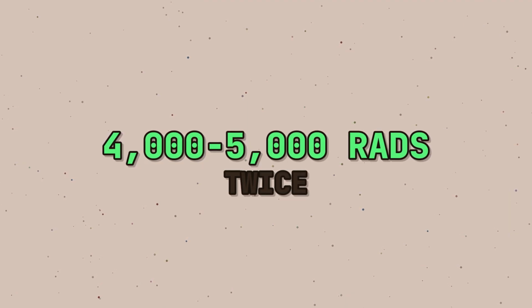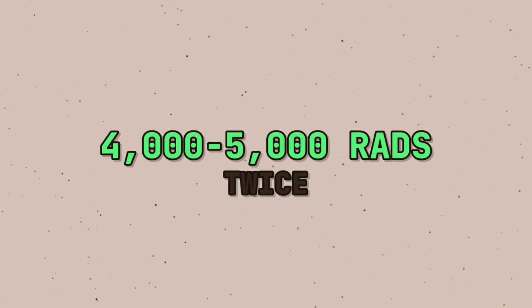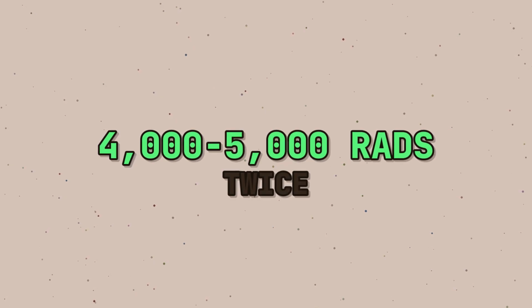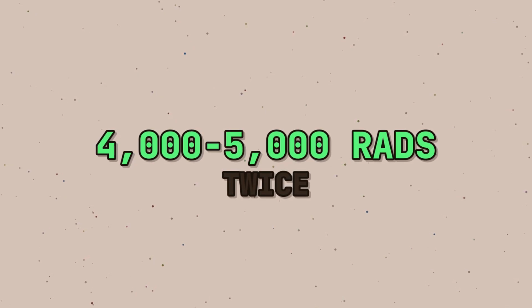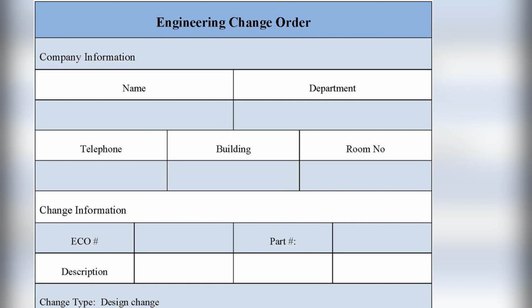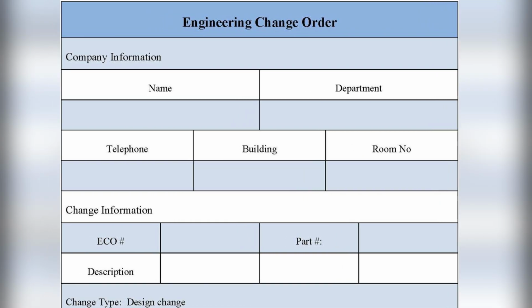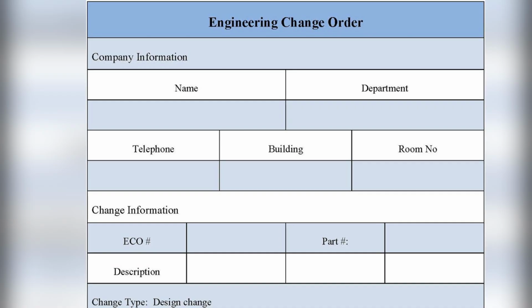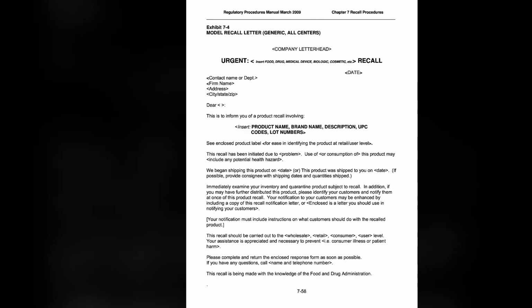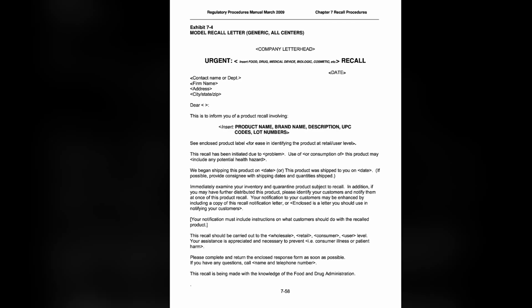Preliminary measurements put the dose at 4,000 to 5,000 rads per attempt, and there were 2 attempts. The patient died that April of complications from the overdose. AECL's own quality assurance manager told the FDA that the changes already designed after Tyler, 9 months earlier, and still not installed, would have prevented it.